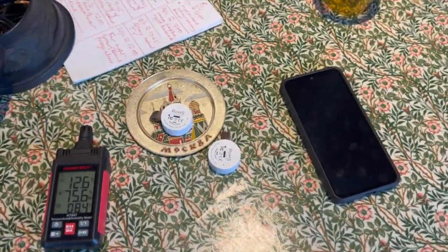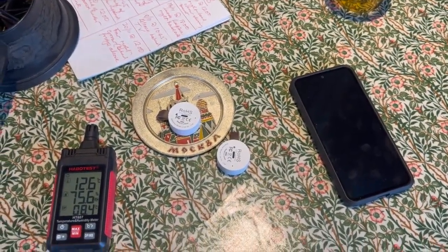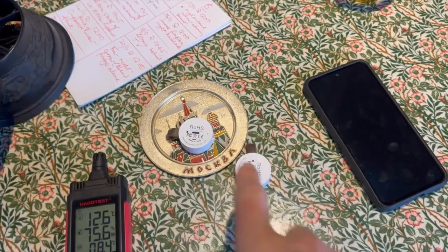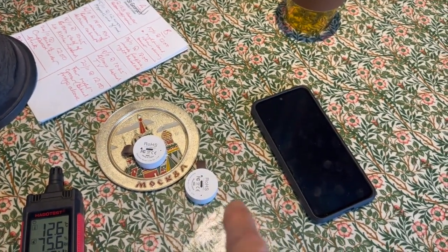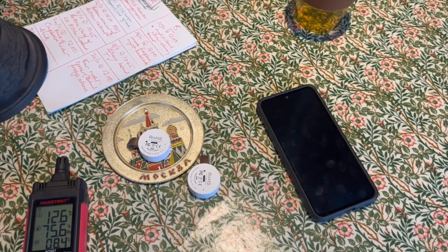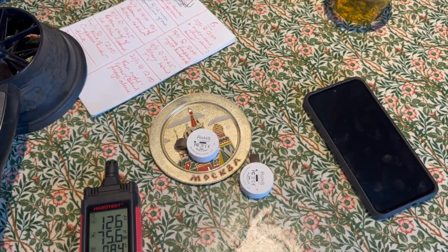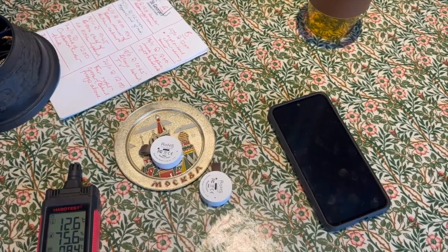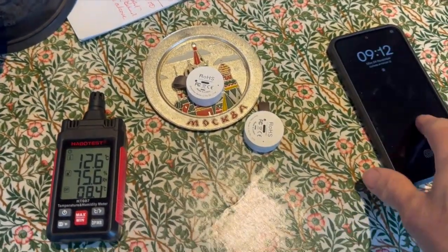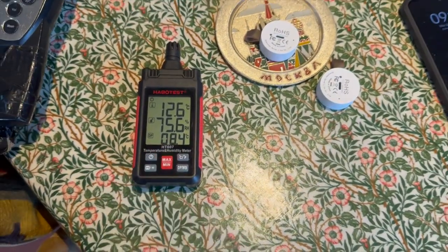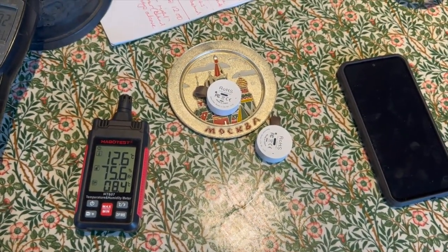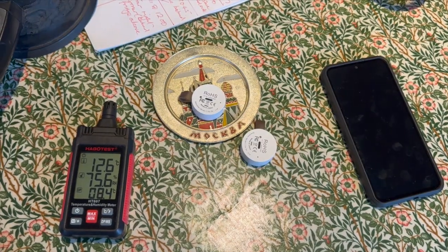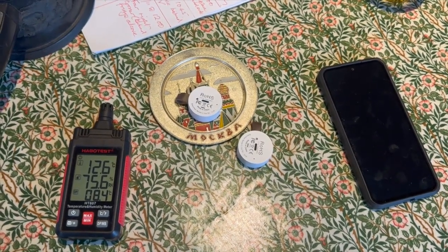So the good news is that this is all fixable. And it's just to do with vapour management. Using the data loggers here will go a long way to help you with vapour management. The key thing to know is that there's something called the dew point. The dew point is a measure of the amount of vapour in air. It's also the temperature where condensation takes place. You can see it on the phone, but I've got it here, and it's showing me that at the moment the internal dew point is 8.4 degrees centigrade. And you need to be keeping that below the outside temperature by increasing ventilation or dehumidification.